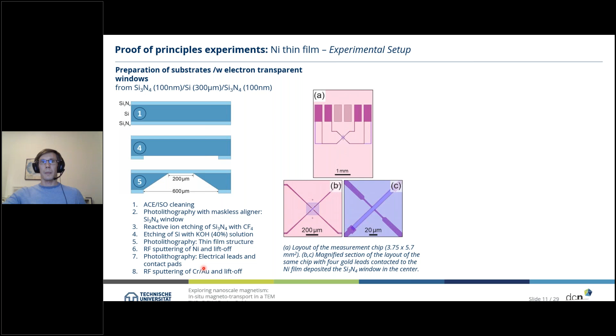All that is then mounted in our prototype holder, which has 6 contacts. As I told you in the design, we're using the 4 outermost contacts to run a current through our sample and measure the voltage perpendicular to that. And that you can see here in the top image. This is a TEM image, where you see the 40 nanometer nickel film. You see the contacts on both sides to run a current through the nickel film. And perpendicular to that, we will measure the voltage as a function of the magnetic field.